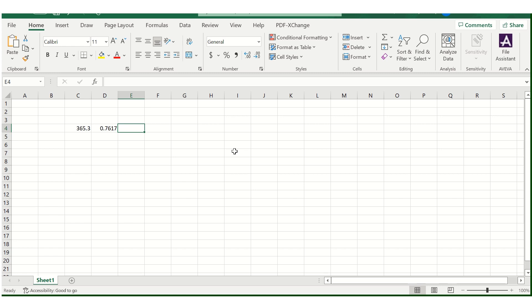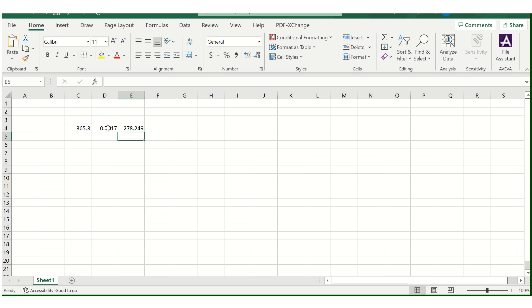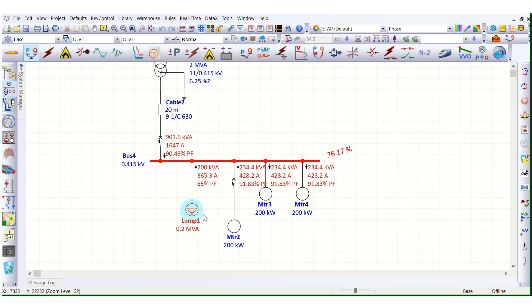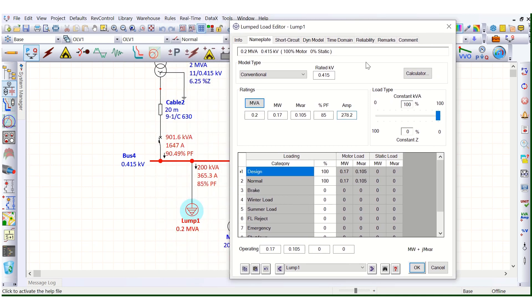Since this is a constant power load, the formula gives rated current divided by voltage in per unit: 278.2 amps divided by 0.7617 bus voltage equals 365.3 amps. This confirms how ETAP calculates the actual current for a constant power load at a reduced bus voltage.